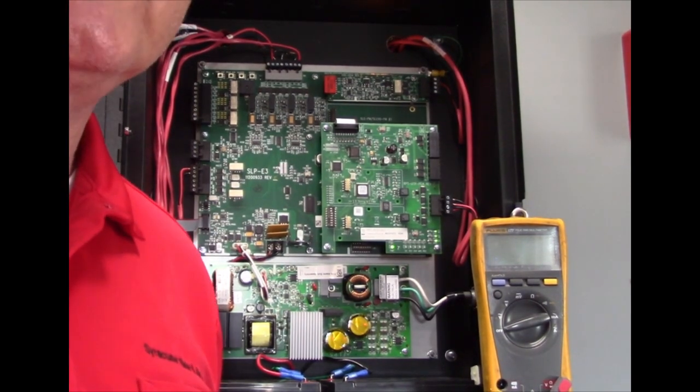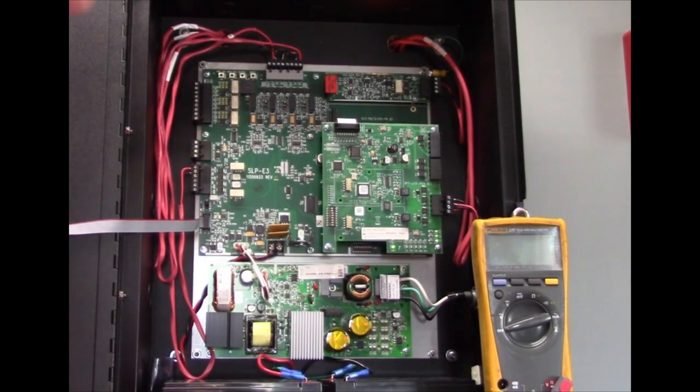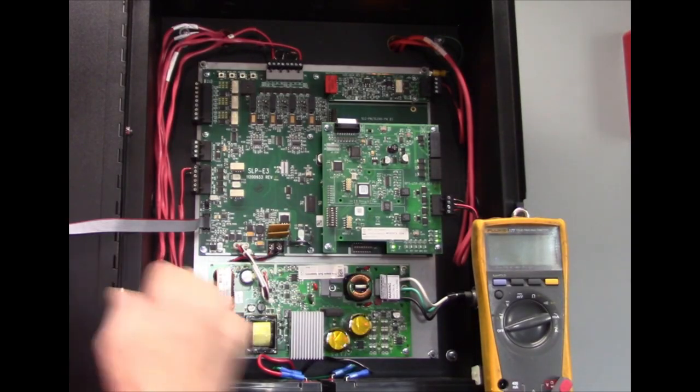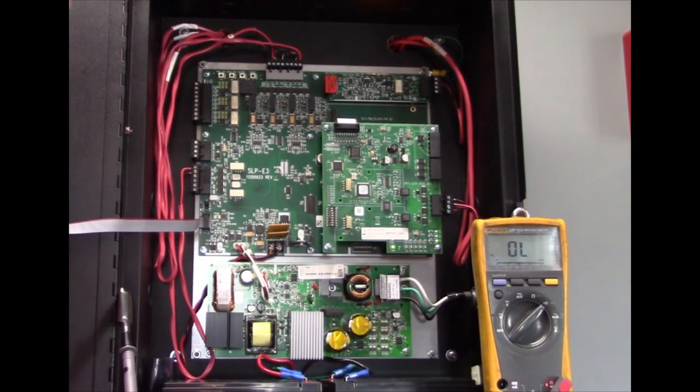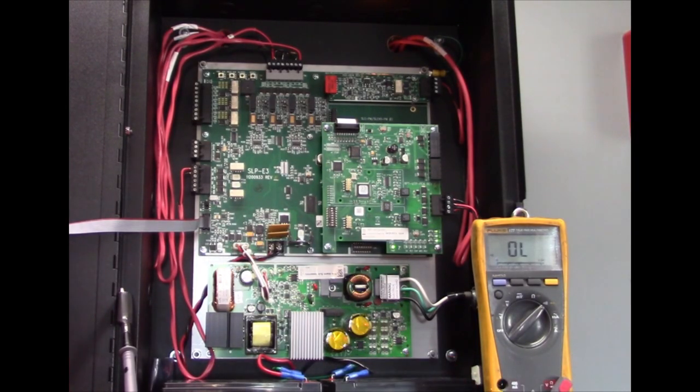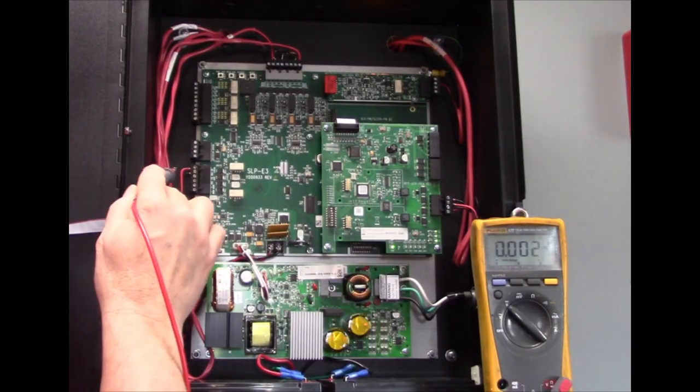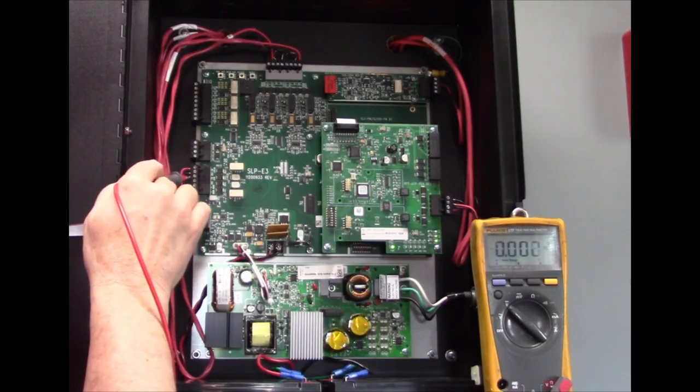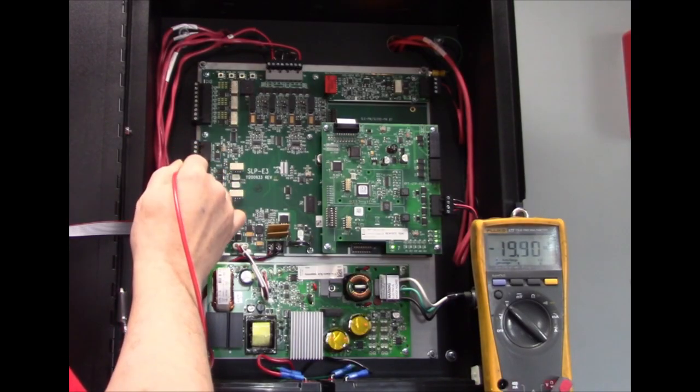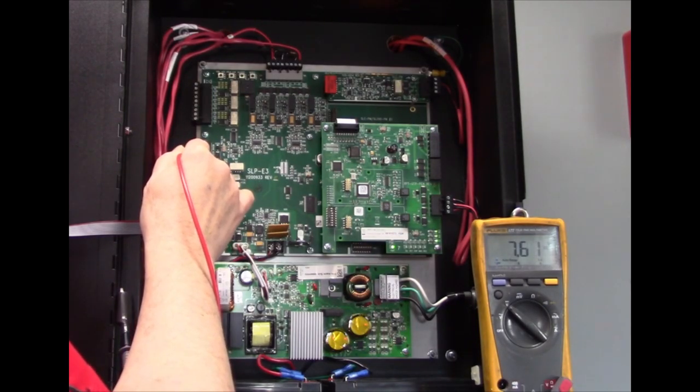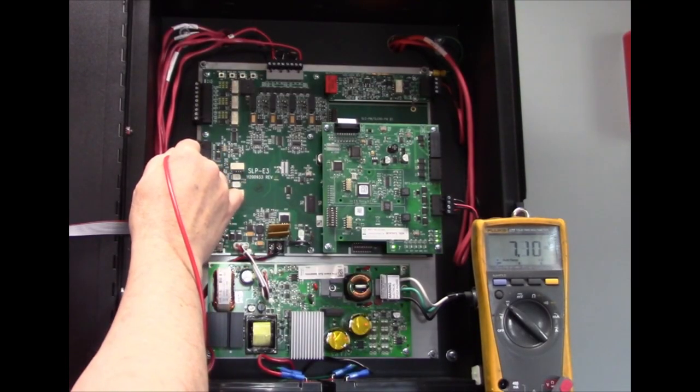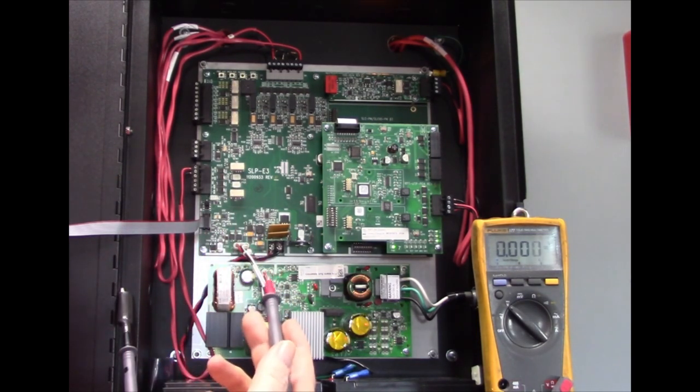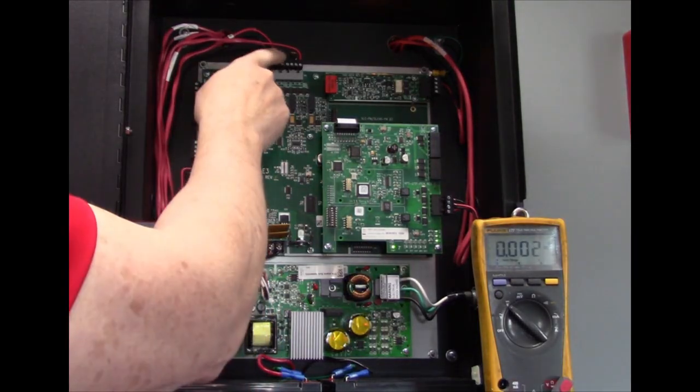The first step in troubleshooting is getting some voltage measurements. So we'll get the meter out. You're going to take one lead and connect it to earth ground. I'm going to connect it to this screw right here, but that's a painted door, so I'm just going to do a continuity check. Make sure that is a good earth ground connection. I can do that by just touching the back plane. I have good continuity there. So now switch your meter to DC volts. And let's get a measurement on the system negative, which this terminal here is our auxiliary power output. The negative wire, we're reading about 20 volts. The positive wire is reading about 7. So you write those numbers down. Those are the bad numbers. What we need to do is find out what is the proper voltage supposed to be when it's not in ground fault.